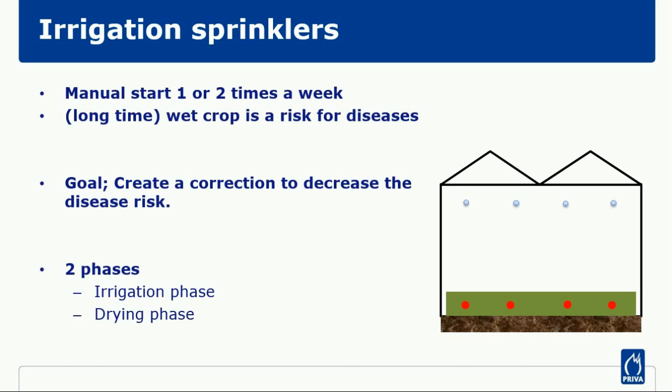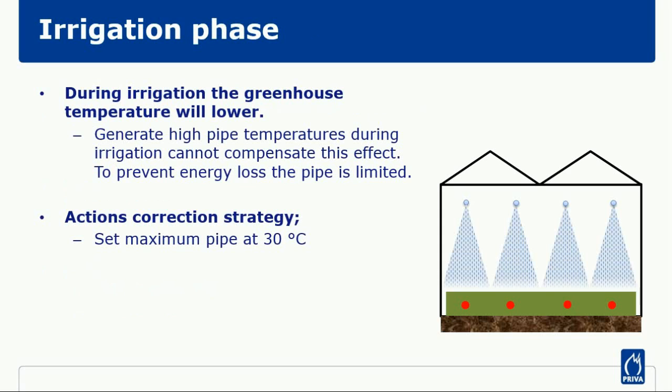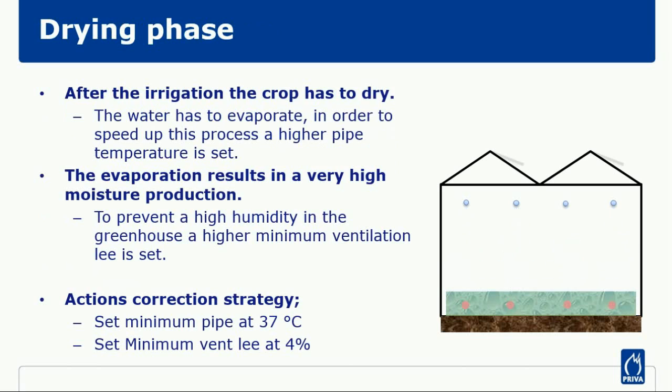During irrigation, I want to limit the max pipe temperature because the tube is not effective when I am irrigating. I will then turn the max tube to 30 degrees. After irrigating, I want the crop to dry as quickly as possible. For this purpose, I am going to use a pipe temperature of 37 degrees with a minimum vent of 4% in order to drain the moisture out of the greenhouse.